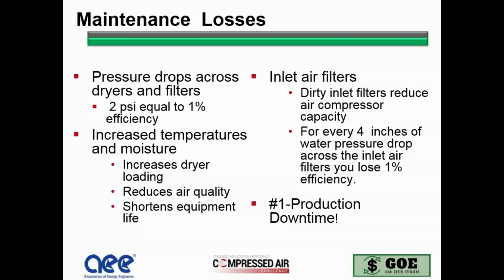So when I put higher temperatures going into the dryer of greater than 100, if I go 20 degrees more and put 120 degrees into the dryer, I will actually double the load. So again, it's very critical that you get rid of that heat. It also reduces the air quality and shortens the equipment life. Inlet air filters to the compressor. Dirty filters reduce the air compressor capacity. And for every 4 inches of water pressure drop across the inlet air filter, you'll lose 1% efficiency. So it is real critical that you take care of that. And then, of course, the number one thing is production downtime.